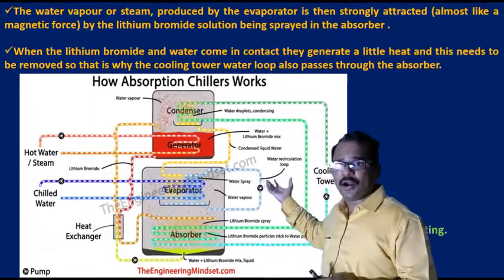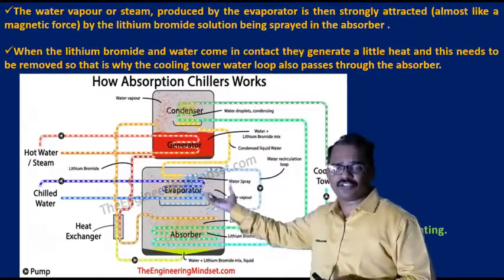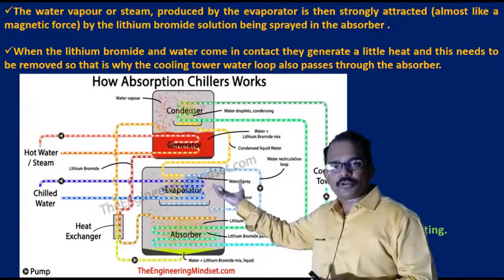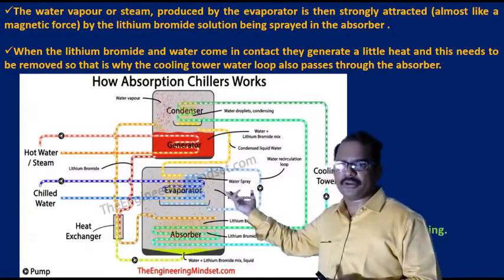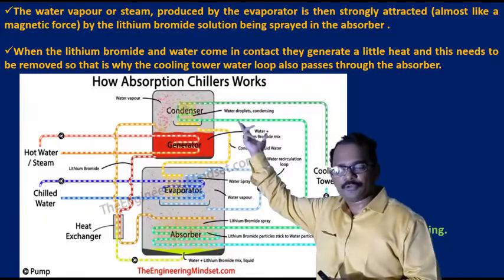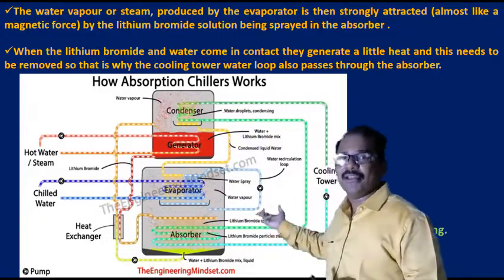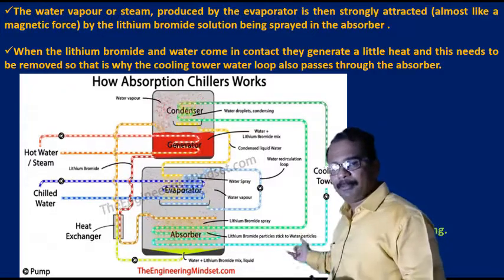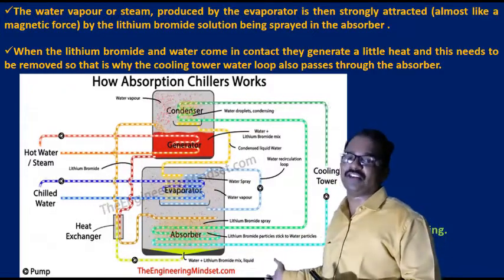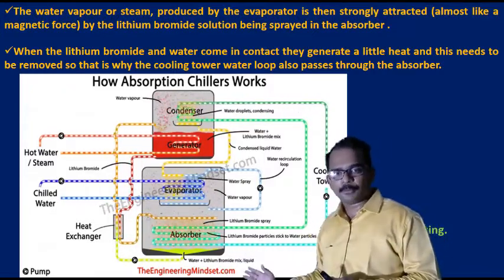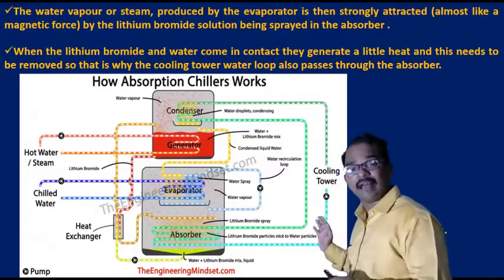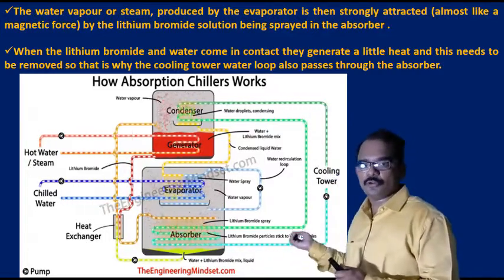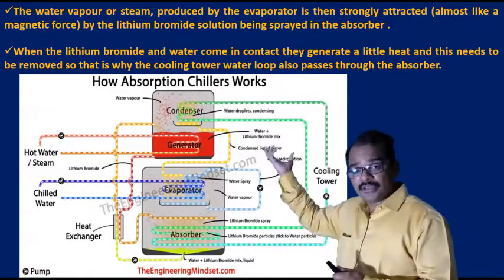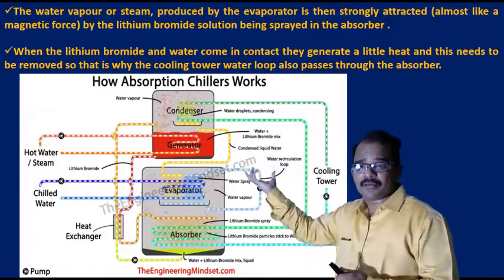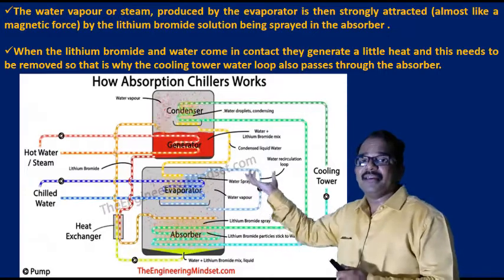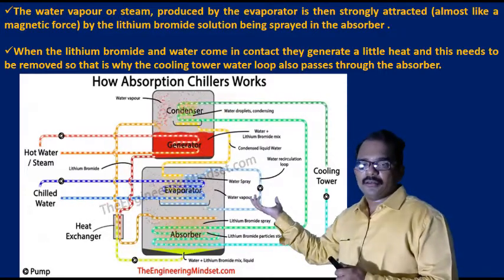So after giving the hot water or steam to the generator section, the lithium bromide and water solution will separate into two components. The water vapor will go into the condenser section, and the lithium bromide will be fed back into the absorber through the heat exchanger. Right. So in the bottommost chamber, we have a lithium bromide solution, and in the top part of the bottom chamber, we have an evaporator where there is steam or water vapor.